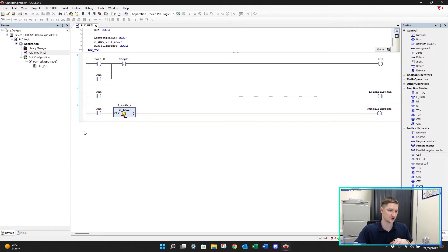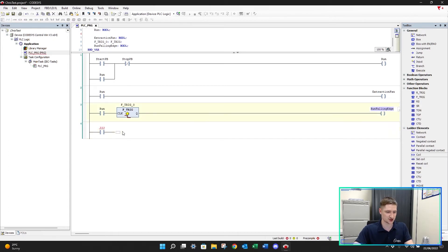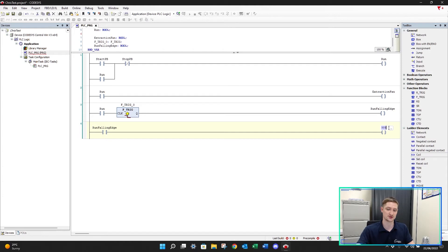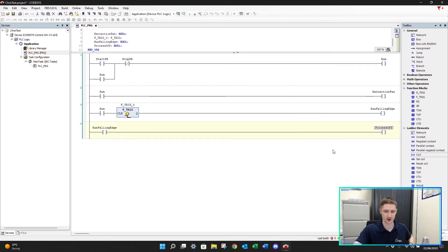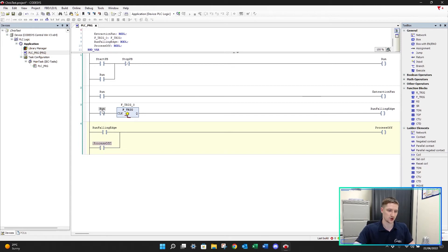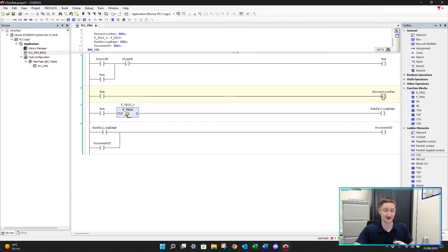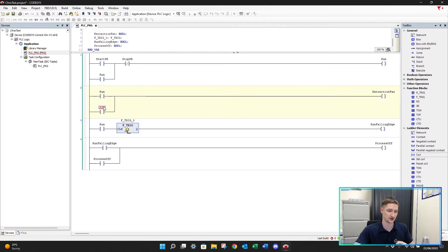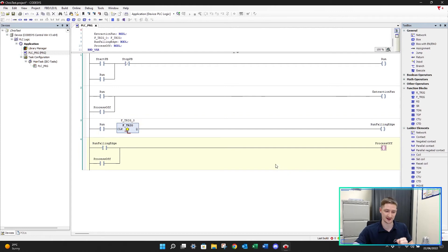I'll then create a new network underneath. When our run falling edge turns on - which is only going to be on for one PLC scan - I then want to turn on a coil. This is going to tell us to continue running our extraction fans; it's telling us that the process is off. Let's call this 'process off'. We'll latch this on with an OR contact also called 'process off'. So when our run signal turns off, it turns on 'run falling edge' for one PLC scan and that latches on our 'process off' signal.